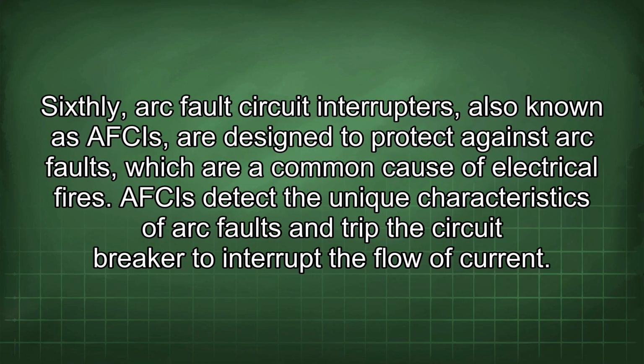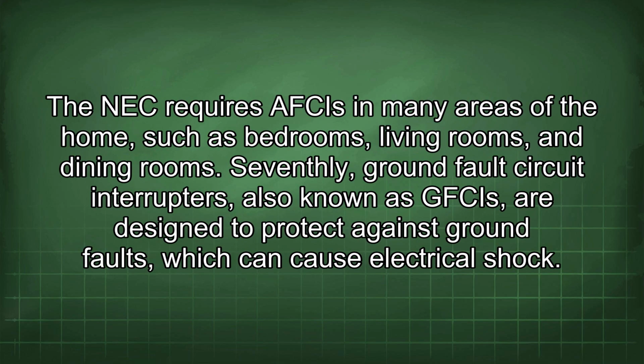Sixthly, arc fault circuit interrupters, also known as AFCIs, are designed to protect against arc faults, which are a common cause of electrical fires. AFCIs detect the unique characteristics of arc faults and trip the circuit breaker to interrupt the flow of current. The NEC requires AFCIs in many areas of the home, such as bedrooms, living rooms, and dining rooms. Seventhly, ground fault circuit interrupters, also known as GFCIs, are designed to protect against ground faults, which can cause electrical shock.